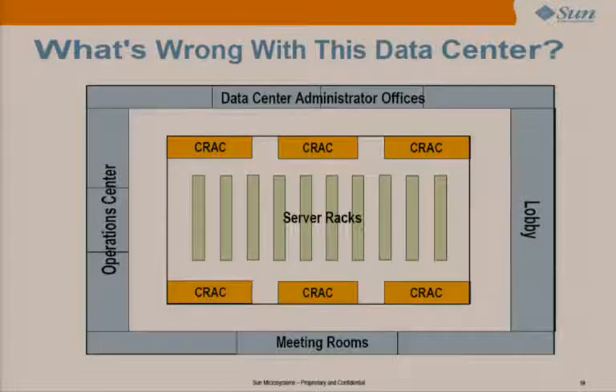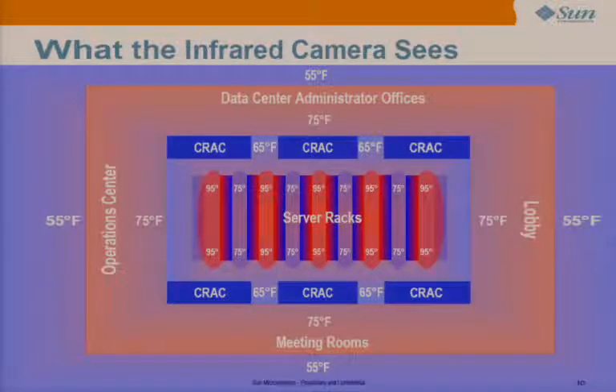If you take an infrared camera picture of this from the top, where the red are the hot zones and the blue are the cold zones, you'll find that the servers generally have an exhaust air temperature of roughly 95 degrees Fahrenheit. This varies obviously, but 95 is fairly typical. The cold aisle temperatures, where you feed the cold air to the servers, are roughly 75 degrees or so. The CRAC units emit cold air at maybe 65, 68 degrees Fahrenheit. And so the data center as a whole is air conditioned.